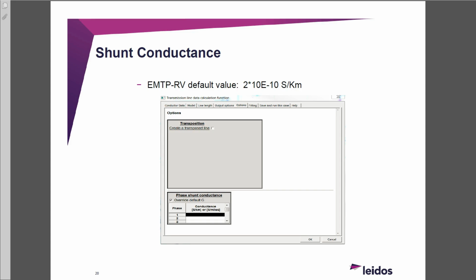So be careful. And what's really tricky with this number is that the newer the line, the more conservative a number you need - the shunt conductance is almost worse. The older the line, the more pollution and the dirtier the insulators, the better it is - meaning less TOV, because it leaks over.